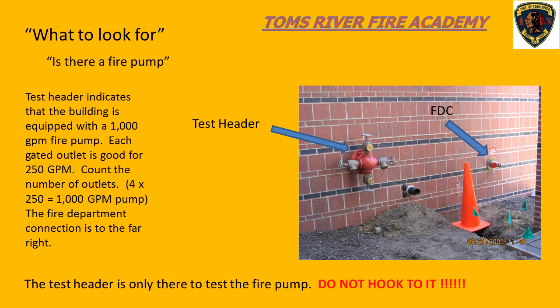Things to look for: here's our fire department connection. Okay, this over here is a test header. This is only here to test the fire pump. So if you see something that looks like this, it's telling you, hey, there's a fire pump in the building. Do not hook up to it. It's only there to test the fire pump on an annual basis.